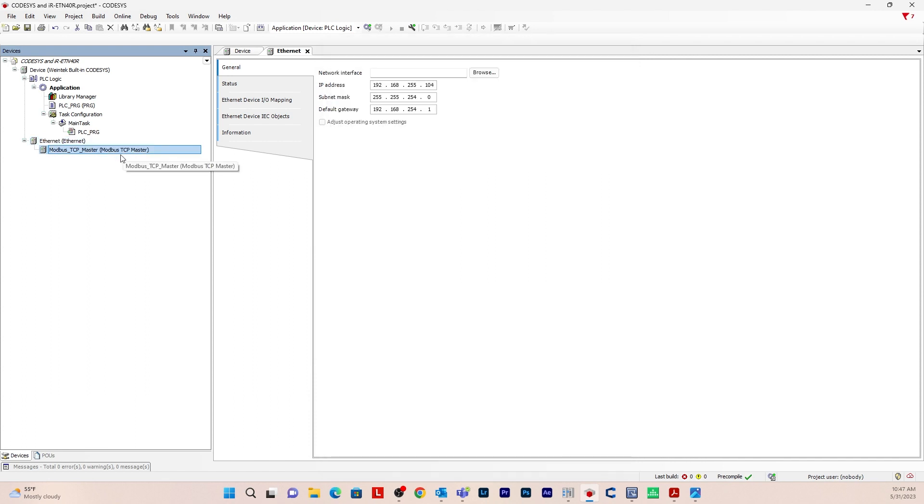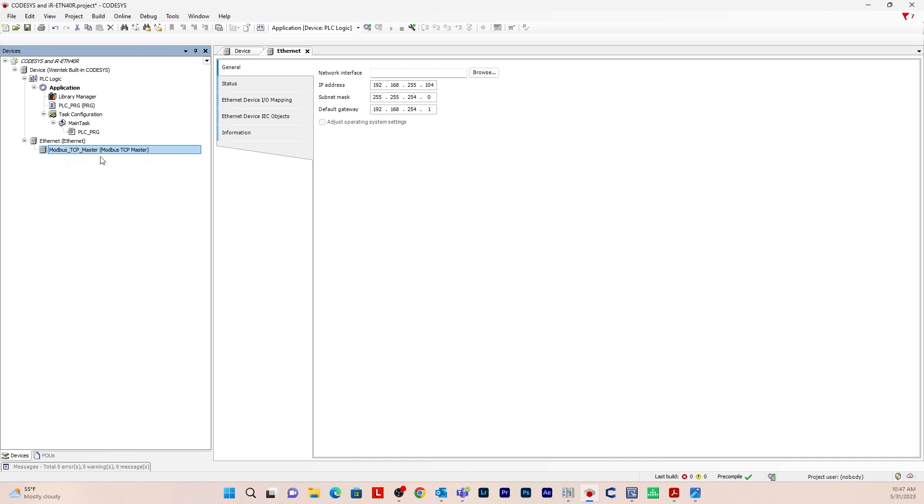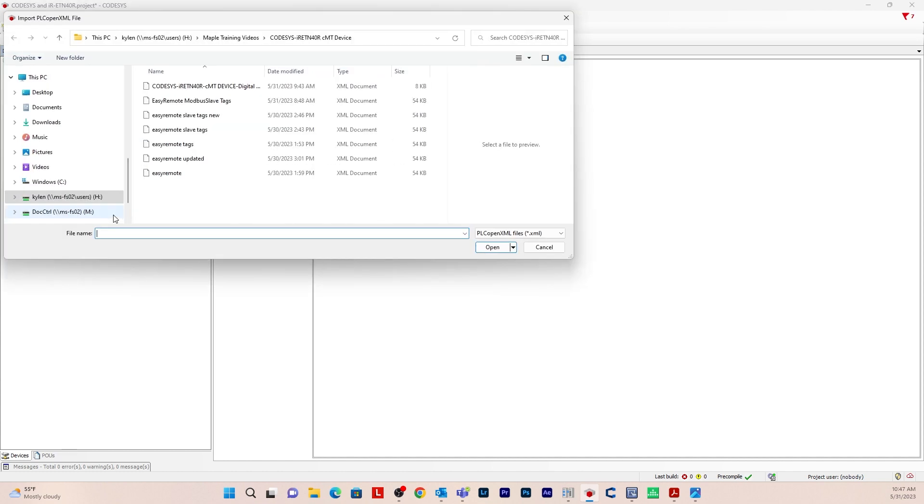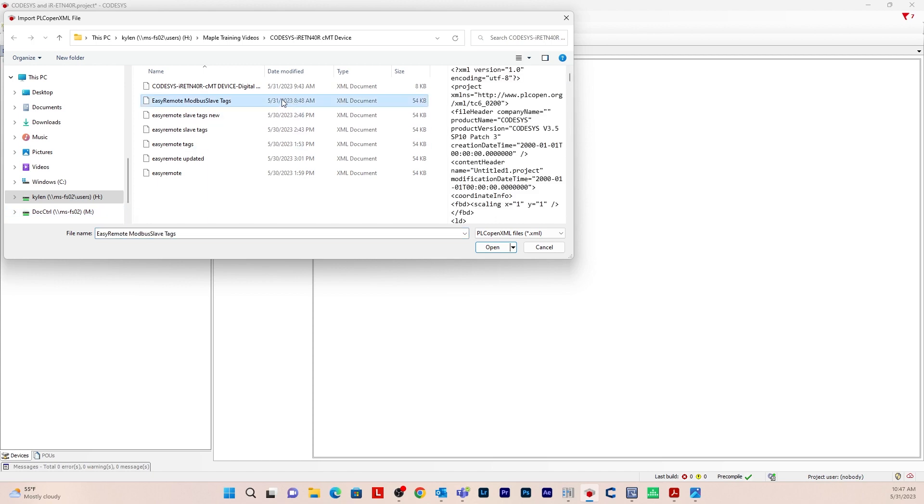So now we want to take that XML file that we exported from Easy Remote. We want to import that into CODESYS to create the slave device here. Make sure you click on modbus.tcpmaster, because we're going to add a device to this. I'm just going to go to project, import plcopen.xml. I'm just going to click the one that I want to import. Hit open.